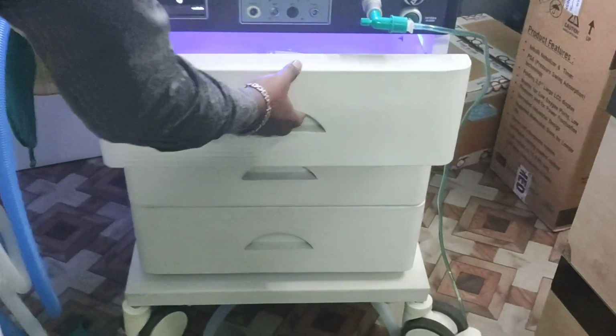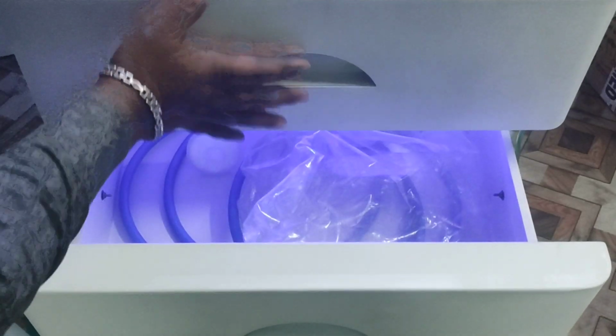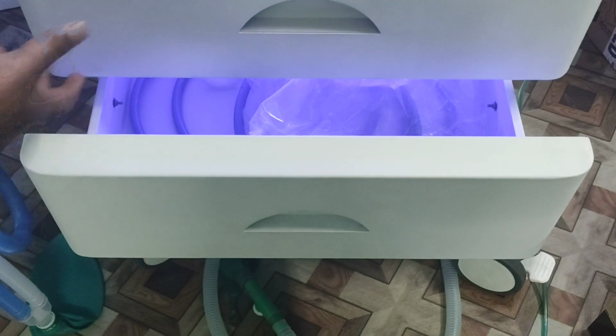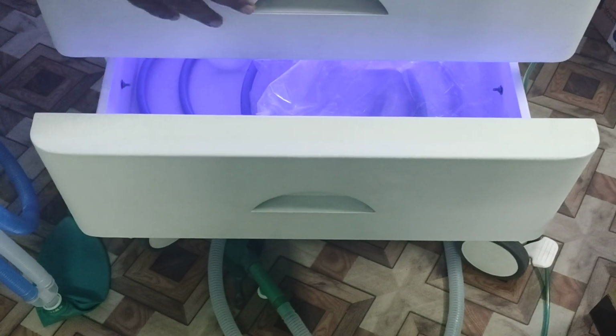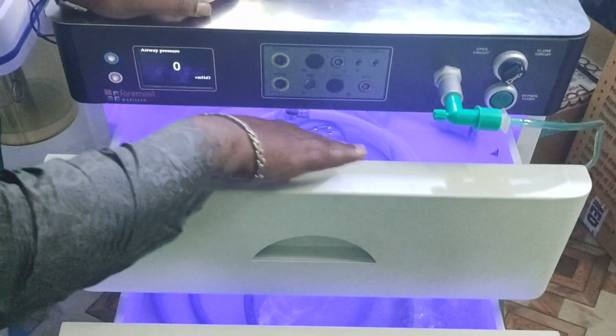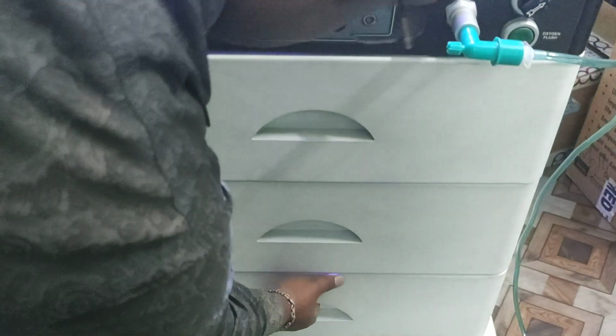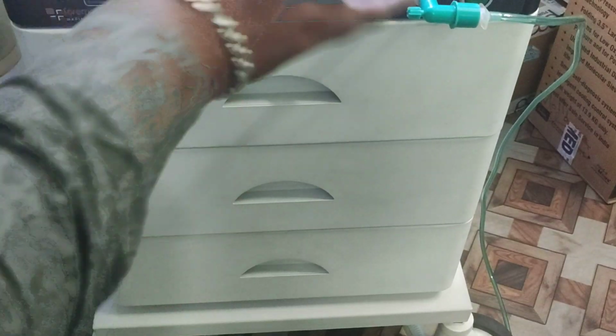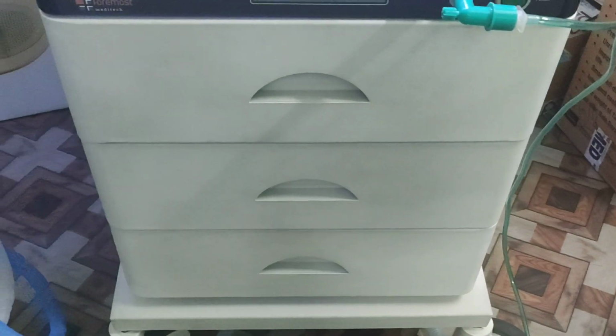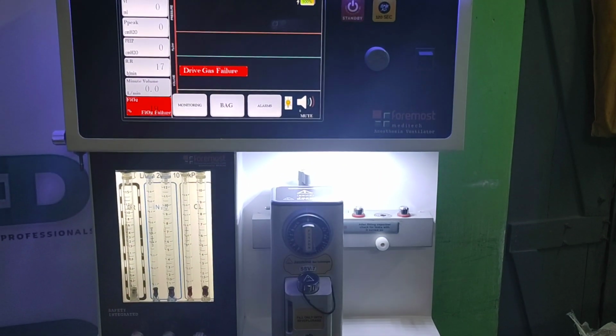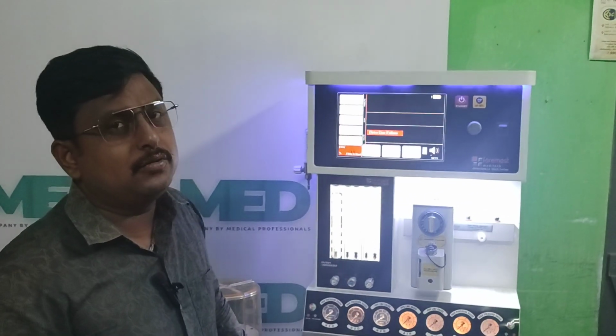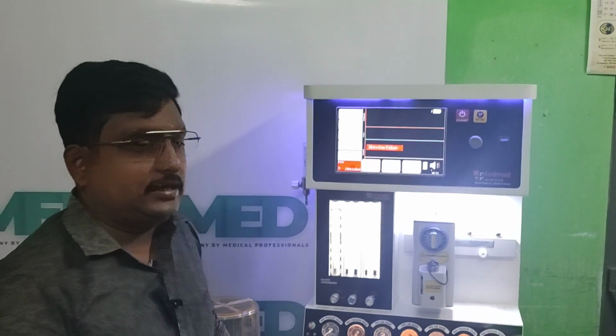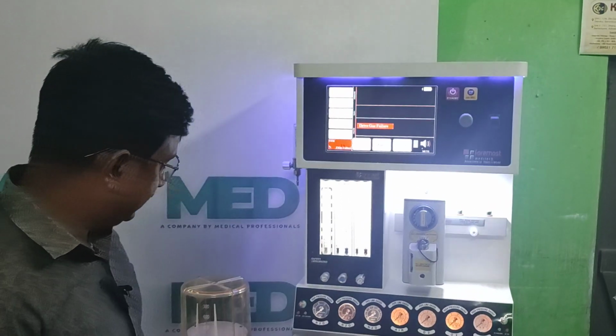Also, the doors are lighted. In the OT, if there is dim light, you can find your accessories and your usables here. The light source is here, so you can easily find things in dark conditions in the OT. The machine is also configured with a light system, so everything is visible in the OT. It's very important. And the machine has a battery backup. If there is a line failure, the machine can run up to 8 hours on the inbuilt battery. So this is again a very important feature of these machines.